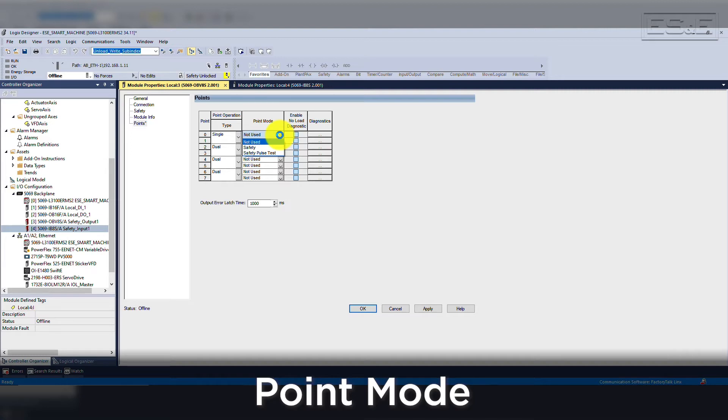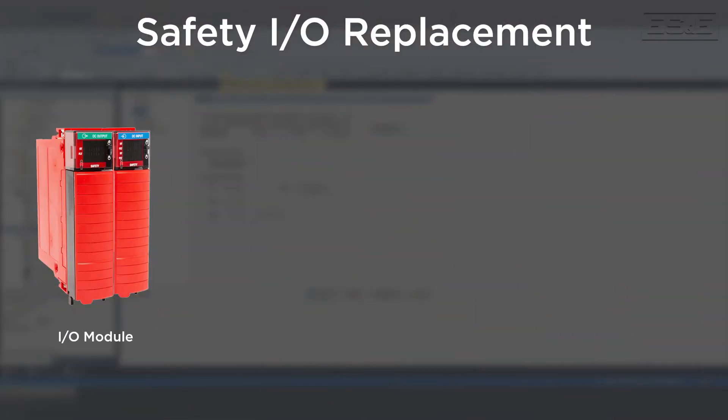This matches the same point modes as input cards. Just like the configuration of the I/O modules are different for safety cards, the replacement of safety I/O cards also have some additional steps. This is due to the safety signature and safety network number. When replacing the I/O module, it changes the safety configuration since the new module is physically different. Even though the card is the same part number, series, and firmware revision, the card may require some action.